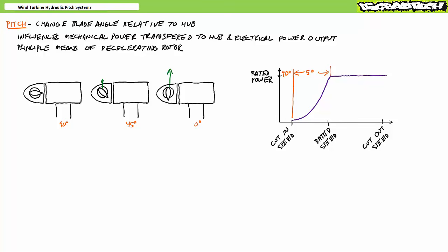This being said, there's a practical limit to the capacity and lifespan of the mechanical and electrical components comprising the turbine, and beyond the rated speed, the turbine starts taking active measures to protect itself and ensure its longevity. This manifests itself as the turbine flatlining output at the nameplate rating at speeds above the rated speed and below the cut-out speed. One of the principal means of regulating output is by pitching the blades such that they progressively shed more and more wind input.